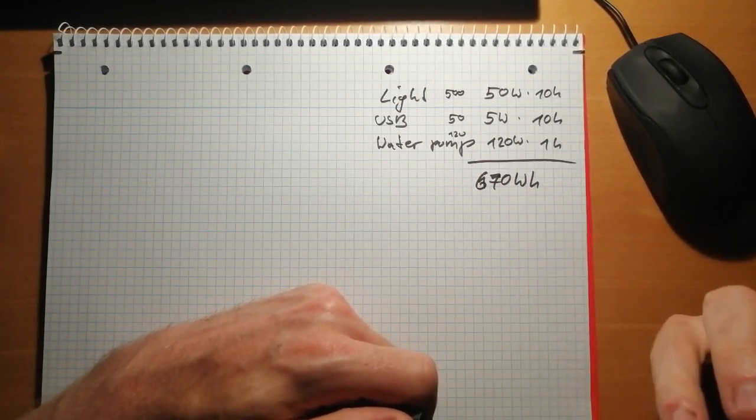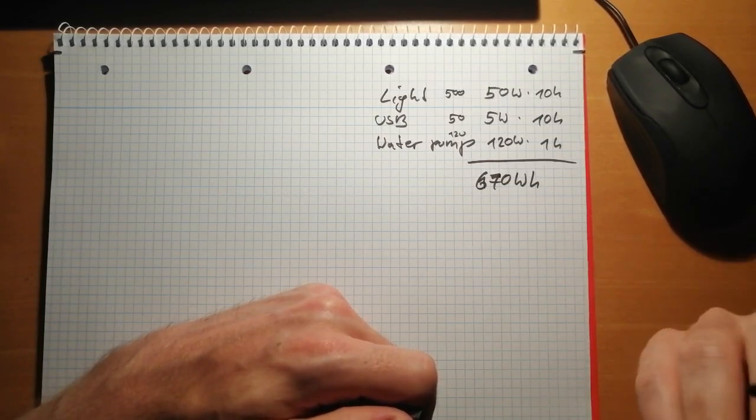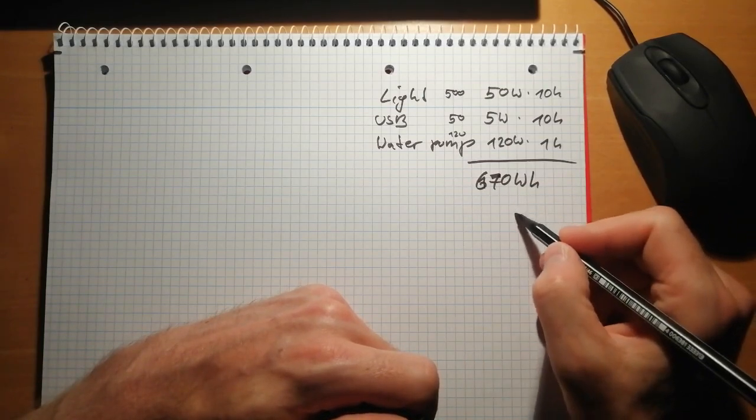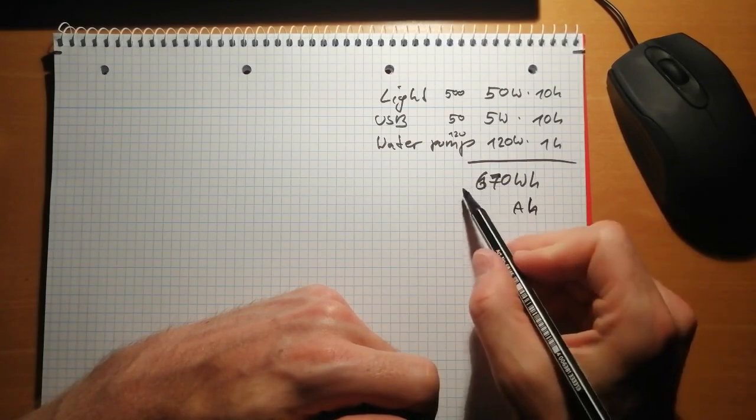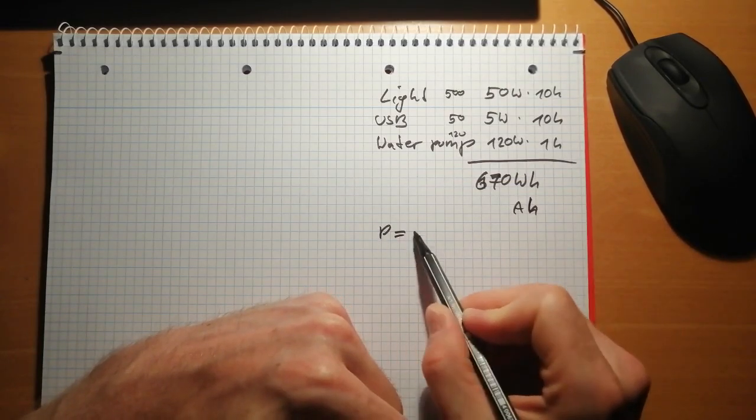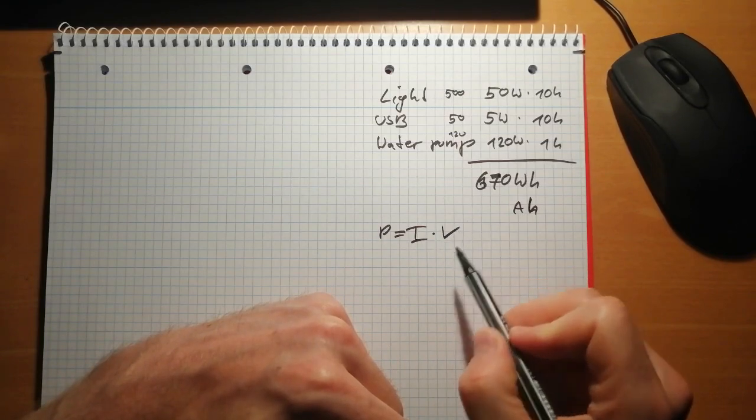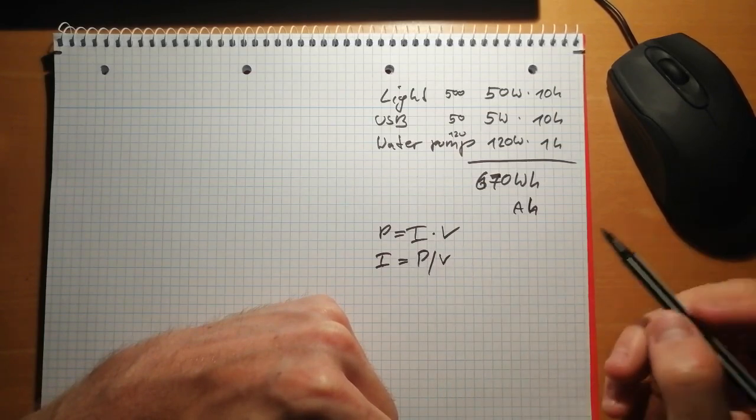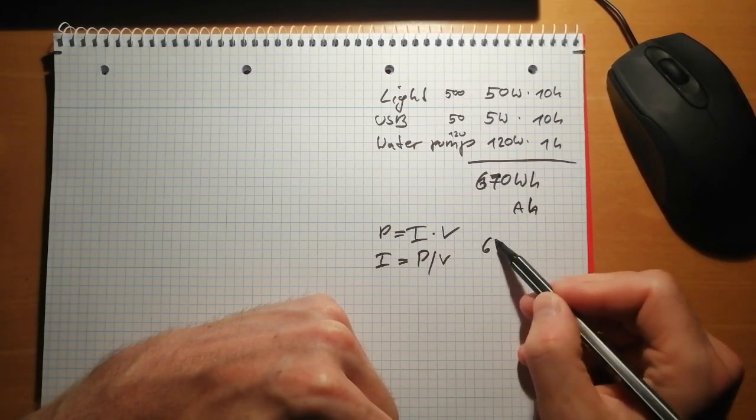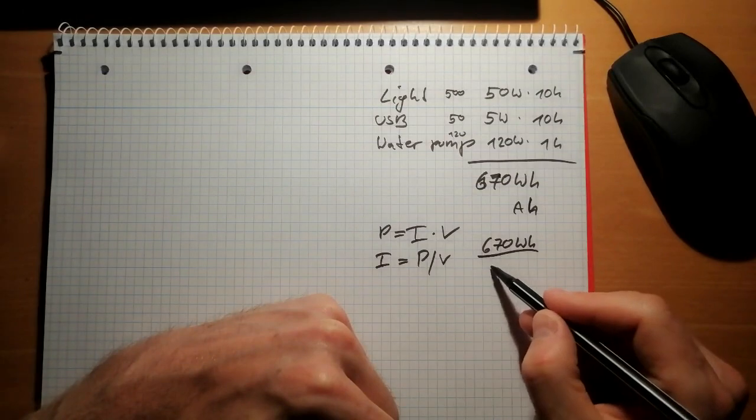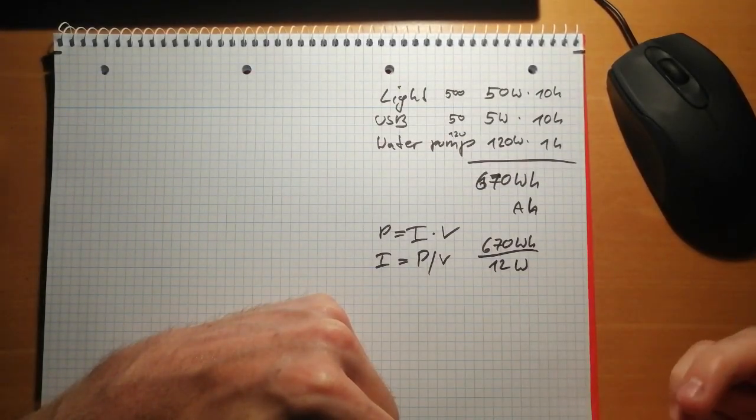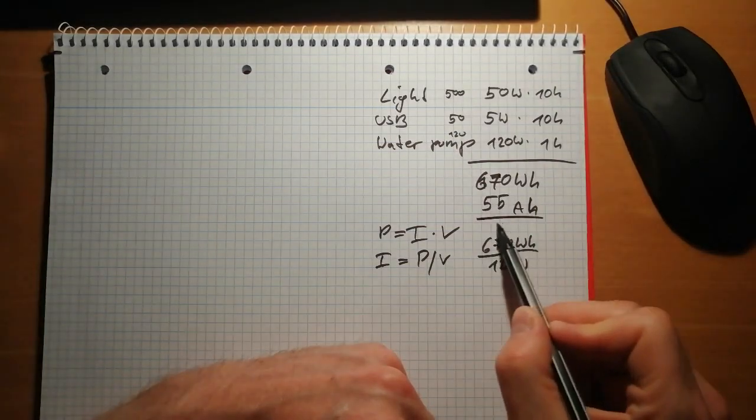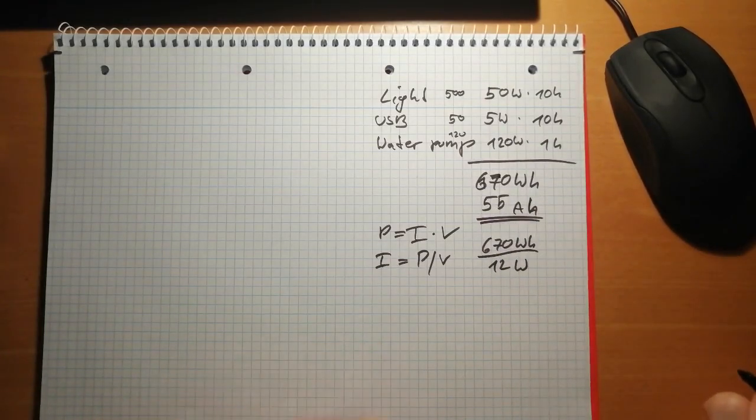As you know, most batteries are specified in amp hours, so the capacity of the battery. If you want to convert watt hours to amp hours, we have to apply the equation power equals current times voltage. And if you want to get the current, we have power divided by voltage. So in this case we have 670 watt hours divided by 12 volts, that is around 55 amp hours. So that's our key number that we have to consider for our battery.